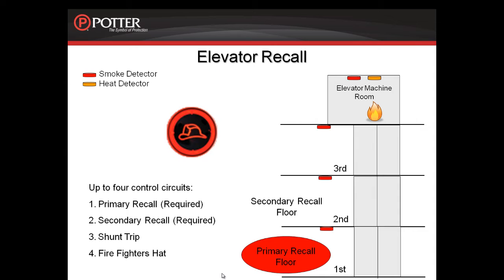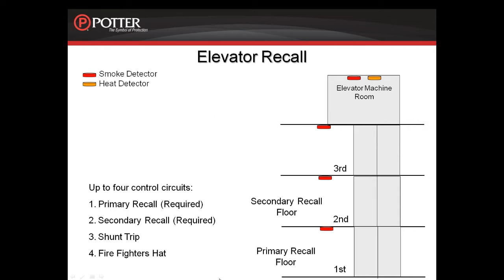In the event that the smoke detector in the elevator machine room activates, we will activate the fire hat in the elevator car by triggering that relay. This particular example pertains to elevator recall for one to three floors, one to five floors, or however many floors. The things to know are your primary floor of egress, the secondary floor of egress, and how many relays are going to be required for your particular job.